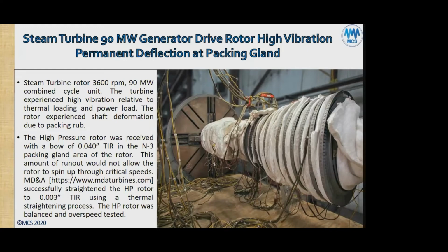The user found evidence that there was a rub, obviously by vibration evidence. The rotor experienced shaft deformation due to packing rub. The rotor was sent to a specialist company, MD&A, and I put their web address there just for information. The high pressure rotor was received and had a fixed bow in the shaft of 40 thousandths of an inch total indicator reading, which means 1 millimeter bend in the N3 packing gland area of the rotor. This amount of runout would not allow the rotor to spin up through critical speeds, so the machine just couldn't operate. You'd be rubbing everywhere.